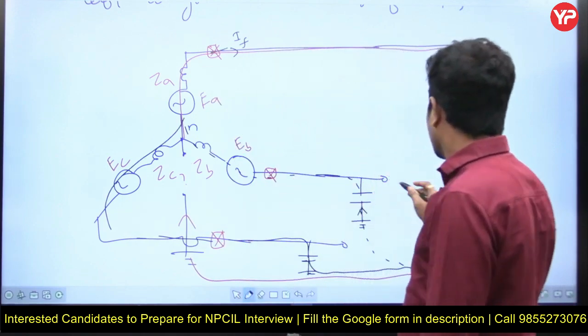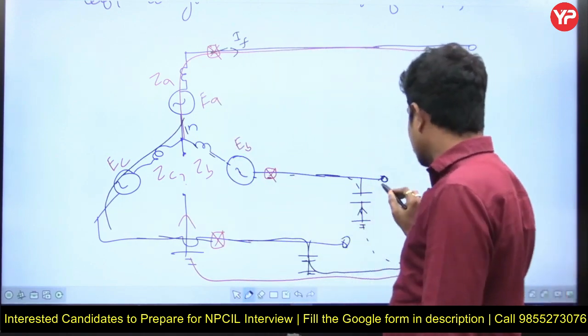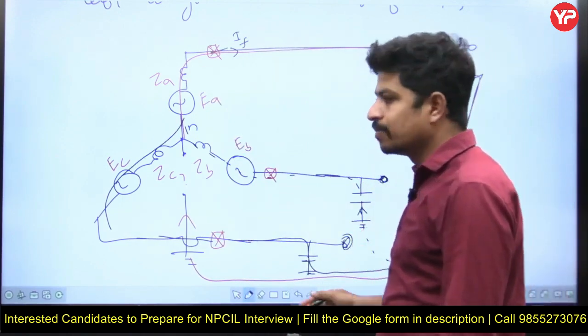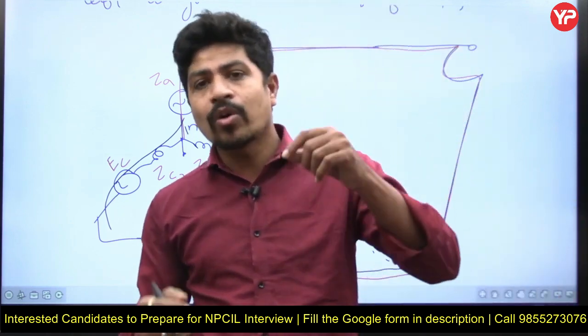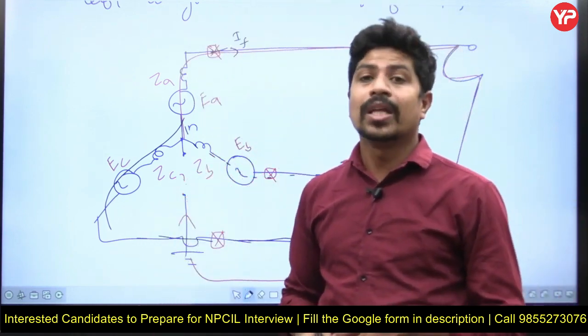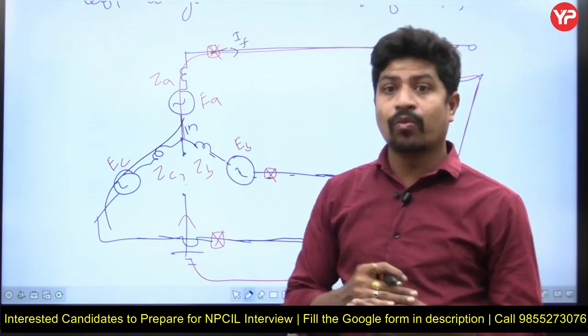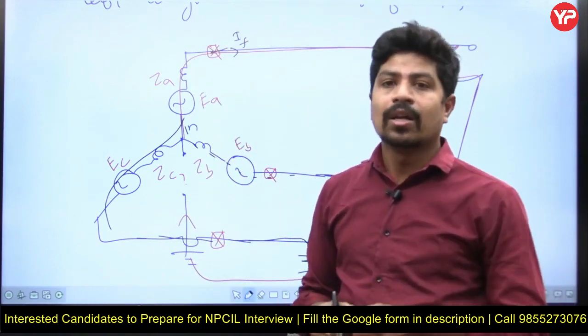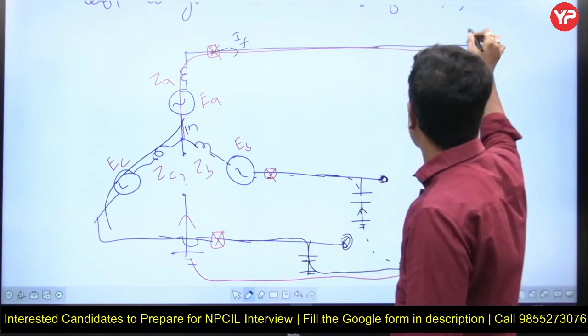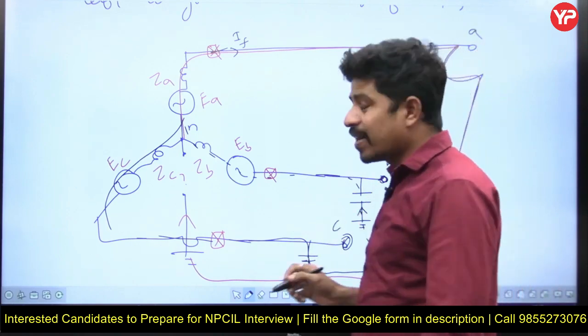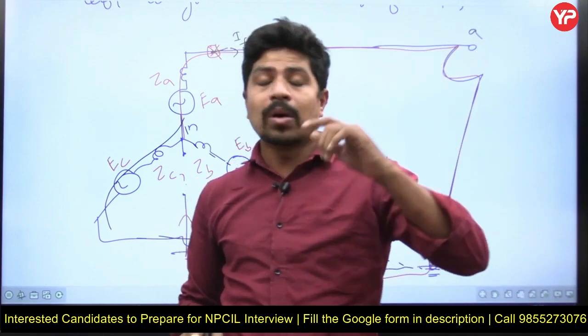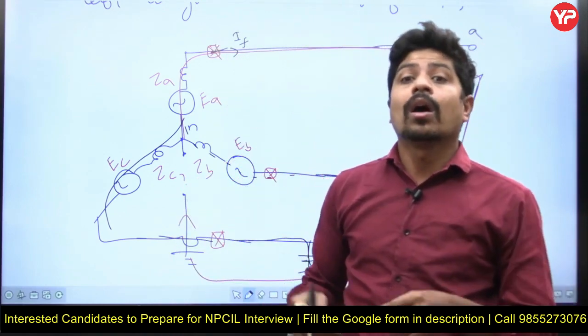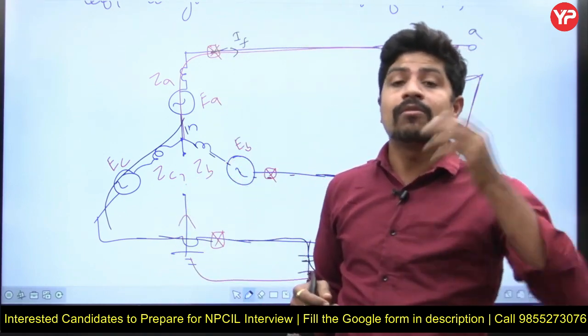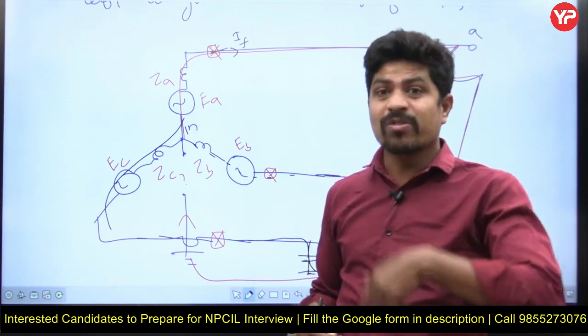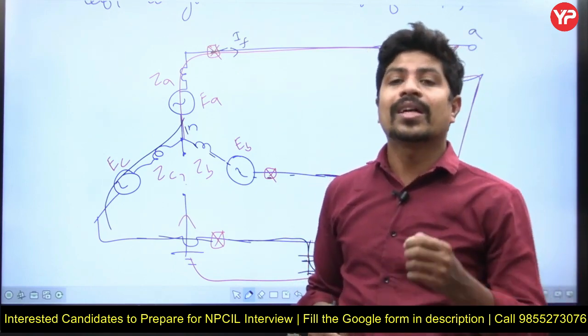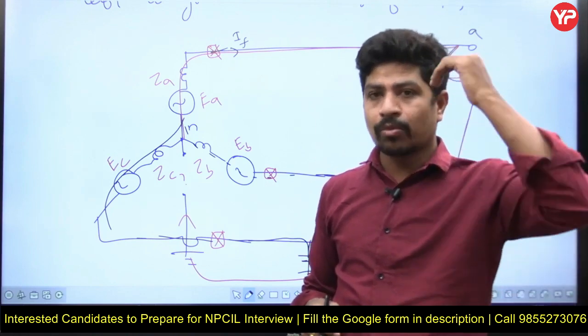Now, if you find the phase voltage of these existing phases, how to find the voltage? Yes, you have to make a closed path. Then, because of this charging current flow, the phase currents. This is phase A, this is phase B, this is phase C. On phase A the fault is there, but on phase B and phase C there is no fault. But because of this small amount of fault current flowing through the capacitances of the remaining two phases to make a closed path, the phase voltage rises up to the line voltage.